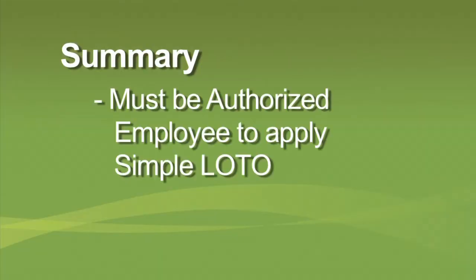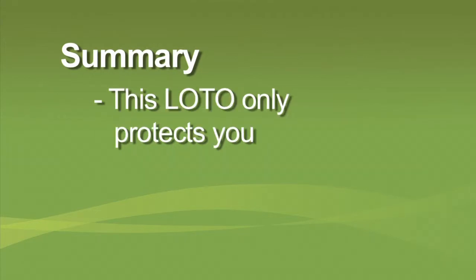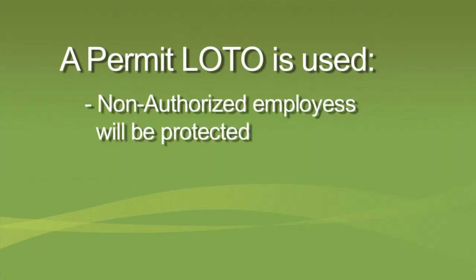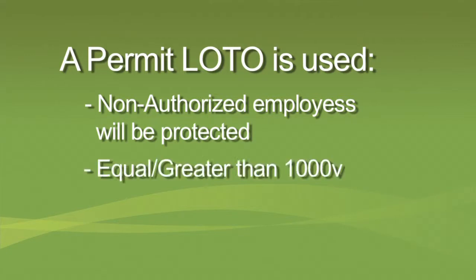To summarize, you must be an authorized employee to apply simple LOTO, and that LOTO only protects you. Because of this, others are not allowed to be protected by your simple LOTO or to remove it. When the simple LOTO requirements cannot be met, a permit LOTO must be used. This means you must use a permit LOTO whenever people who are not authorized employees must be protected.